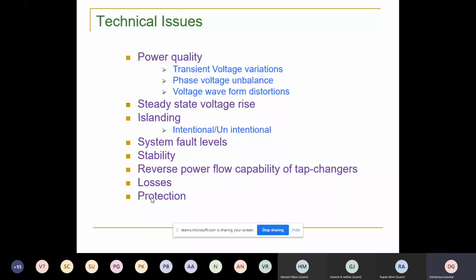Another important thing is the future grid will be DC. You will have in-home level DC, grid level AC, so it's a hybrid AC-DC grid. But DC does not have a natural zero crossing, which creates problems in circuit breaker operation. Designing circuit breakers becomes a very important task, and there are a lot of issues related to protection. Your entire relay system will not coordinate properly because of generation coming on the feeder. These are all going to be issues.